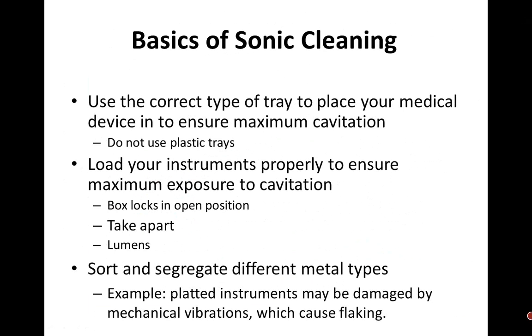Load your instruments properly: open the box locks, take apart the takeapart instruments, and open lumens. I'm actually going to show you some very good pictures on how you should load your sonic cleaner and ways to enhance that sonic activity. If you don't open it, it will not clean as well as it should be. You must sort and segregate different types of metals. Many people put plated metals or probes in there, and the mechanical vibrations or the cavitations can cause flaking.